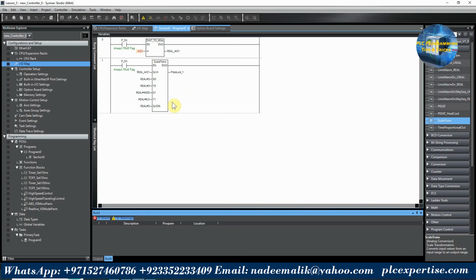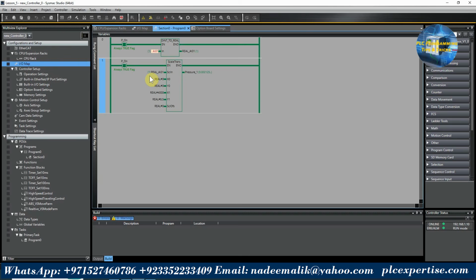go online with the PLC. As you can see, as I increase the pressure, our raw value is increasing, and we are getting the scaled pressure value here in the pressure_1 variable. And at around 5 volts input, we are getting 2000, which is half of this 4000, and we are getting exactly 4.25 bar. Now if I increase to max 10 volts, we are getting 8.5 bar, which is the maximum pressure range of our sensor.